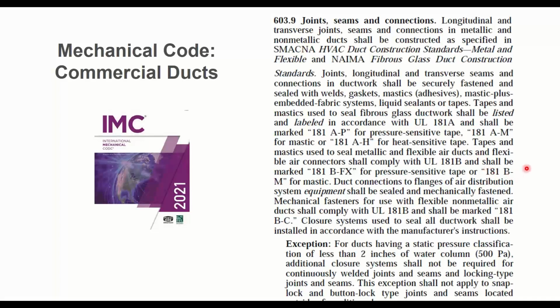Tape is allowed. There is some confusion on that. People will say, oh, no, you can't use tape. When we say you can't use tape, we mean you can't use crappy tape. You can't use actual duct tape. By the way, duct tape can be used everywhere for everything in your life except ductwork. It doesn't go on ductwork. It's for everything else. And you can't even use the low-end foil tape. You have to use UL 181 listed tape if you want to go the tape route. But you can, in fact, use it.